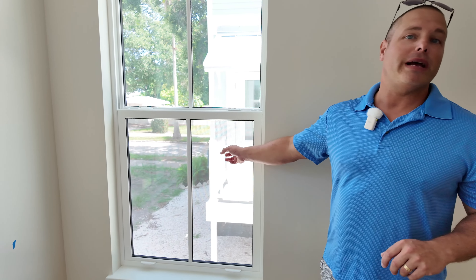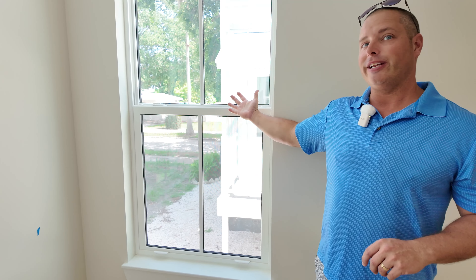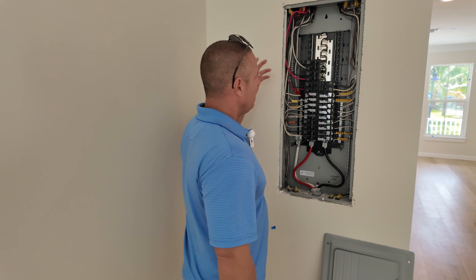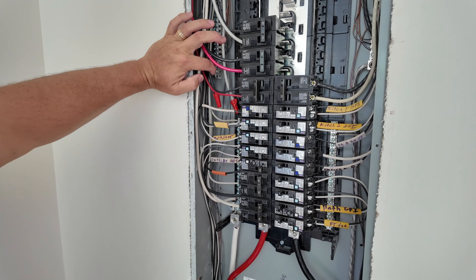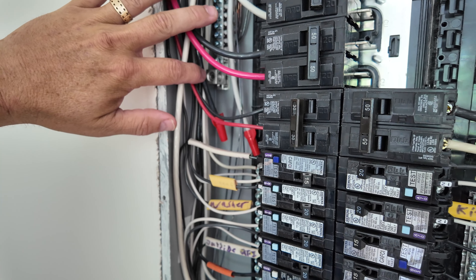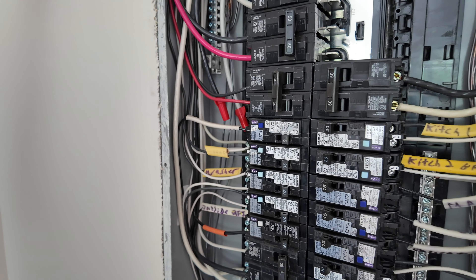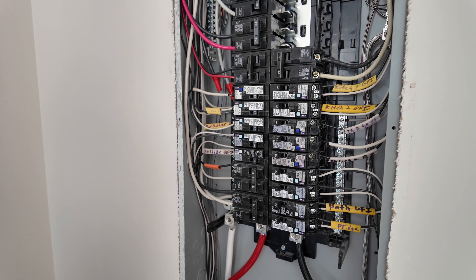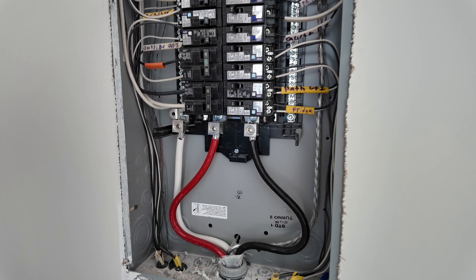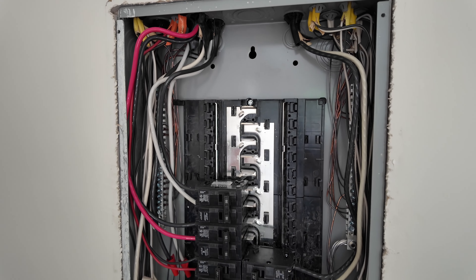These windows do really well for energy efficiency and sound. We have some extra wires that are not connected — I noticed this ran upstairs to where the hot water heater is. When I opened this up, I expect everything to have a home and be in its place. We don't like to see wire nuts or wires dangling — we want it all straight, neat, orderly, clean and ready to go. I left this open and I'm still trying to figure out the intended purpose, because you don't typically run extra wiring on new construction. We have wiring diagrams and plans and we stick to them. The main switch is outside by the meter — that's the new code.